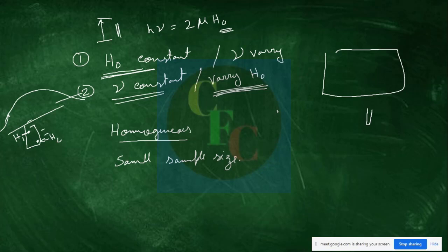So these are mostly very narrow tubes, and the sample is filled 2 to 3 centimeters. Mostly liquid samples are done there. So now our work is to maintain a homogeneous field only in this part. That is enough, isn't it? So this is now easier.